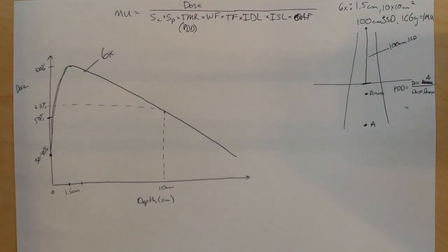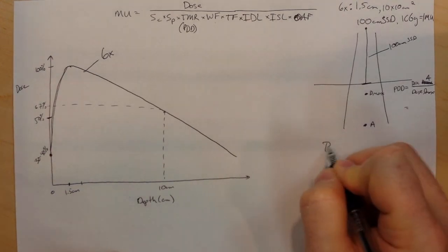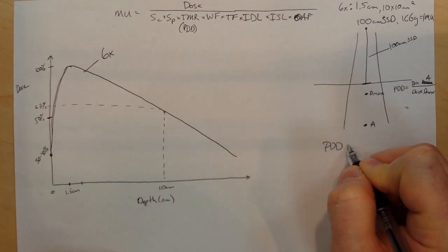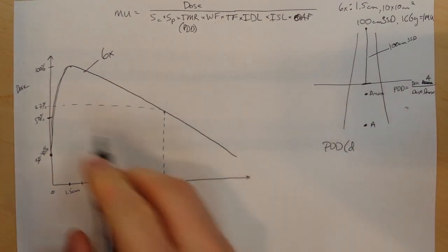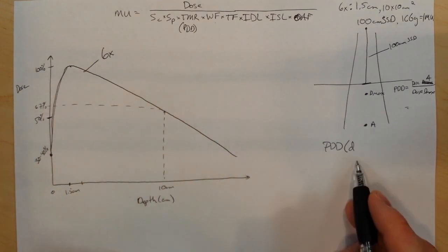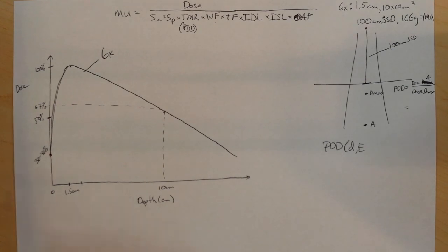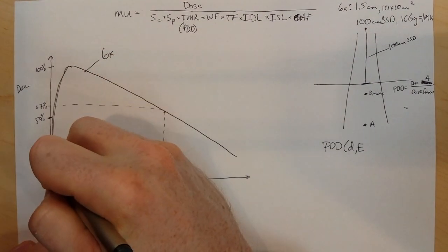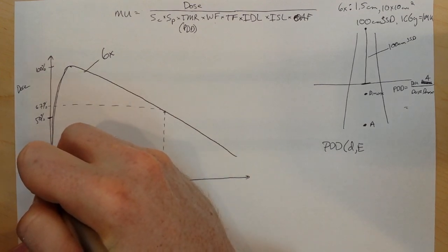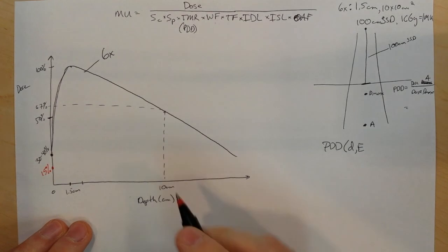Okay. What happens if I change the energy? Well, what's percent depth dose dependent on? It's going to be dependent on depth. As you can see, as we change the depth, I get a change in percent depth dose. It's going to change with the energy. If I have an 18 MV beam, now my surface dose is right around, we'll call it 15%, 15 to 20%.